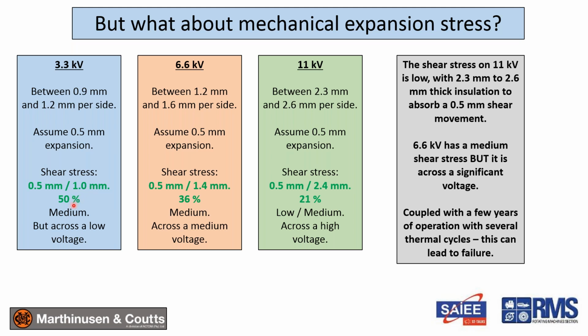So it's quite substantial. 6.6 kV, 0.5 millimeter over 1.4 millimeters. So it's 36%. It's sort of medium stress. And 11 kV is very low. It's 21%, 0.5 millimeter over 2.4 millimeters. So imagine that coil trying to shear the insulation. In one case, it tries to shear 1 millimeter. The other one, it tries to shear 1.4, and the other one, it tries to shear 2.4.